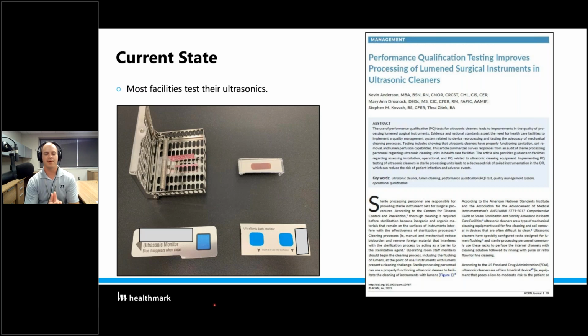All right, so remember, going back to the three basic functions, and that AAMI says to test critical parameters. It also says that fluid flow through the lumen adapters and all of that is another key performance indicator for ultrasonic cleaners. We found out after lots of visits to other facilities that they were testing commonly for soil removal, but they were not testing for soil removal within lumens. But many places have ultrasonic cleaners that are equipped with this function, and a lot of them are using it, which is great. But we just recommend that if you're going to use it, you should test it and make sure that it is actually performing properly.